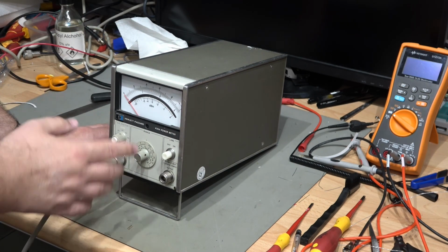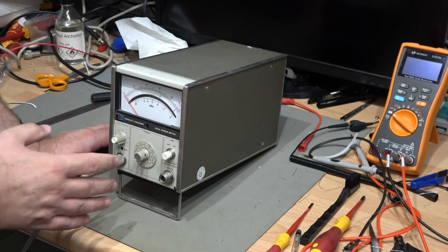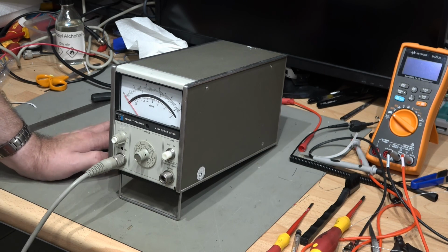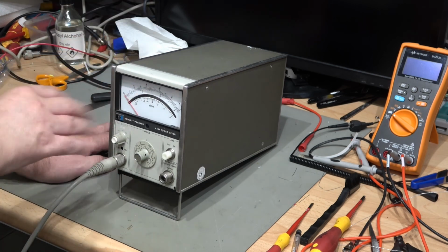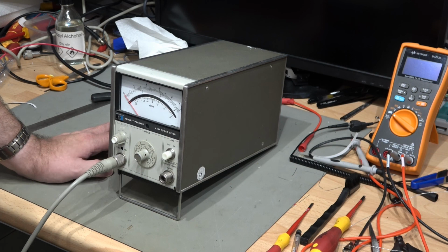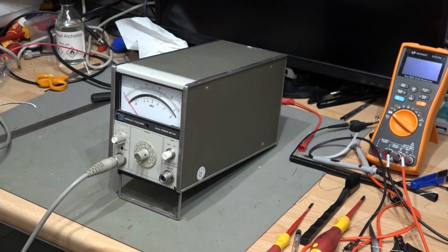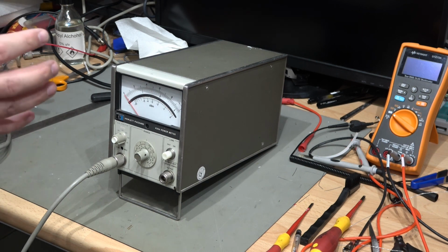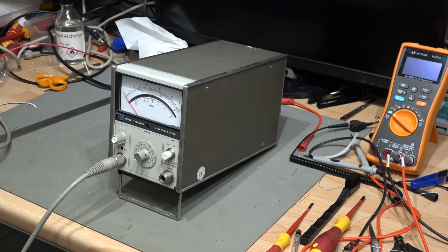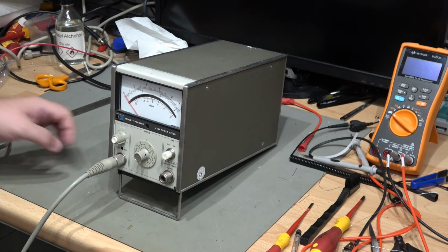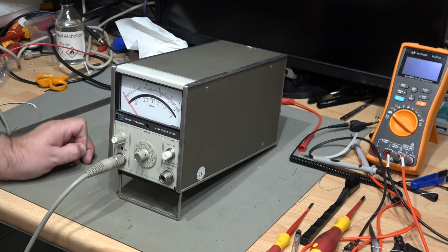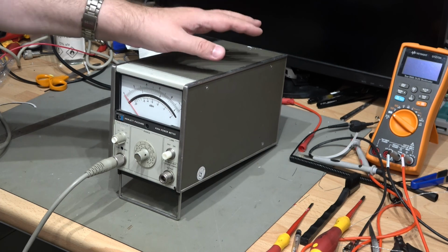And then I started checking all the scales, still had some problems with the microwatts, the last 3 microwatt scales. And I decided that it was probably down to capacitors. And I popped all of the tantalum capacitors in the entire device out, tested them, and replaced anything that had high leakage. I suppose the point to make there is that when you pop the capacitor out, pop it in a capacitor meter, it measured absolutely fine. It was only when I actually connected it to a microamp meter in my multimeter, put some voltage through it, maxed the voltage out for each tantalum, that I was able to measure that the leakage was far too high on some of them. Anyway, I managed eventually to source some tantalum capacitors. These are axial metal can tantalum capacitors, very difficult to get hold of, very expensive, which is why I only replaced the ones that needed it. But yeah, this is about 50 years old, and it's probably good for another 50 years now.